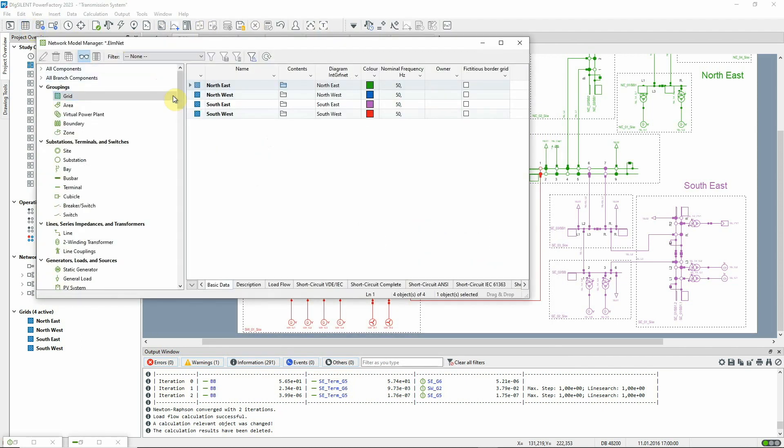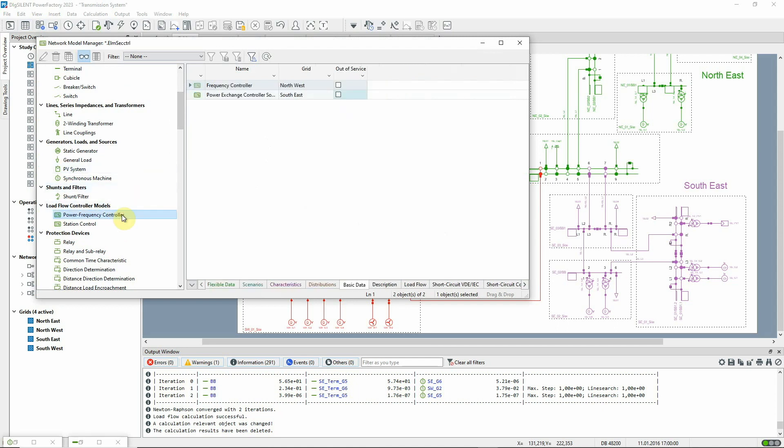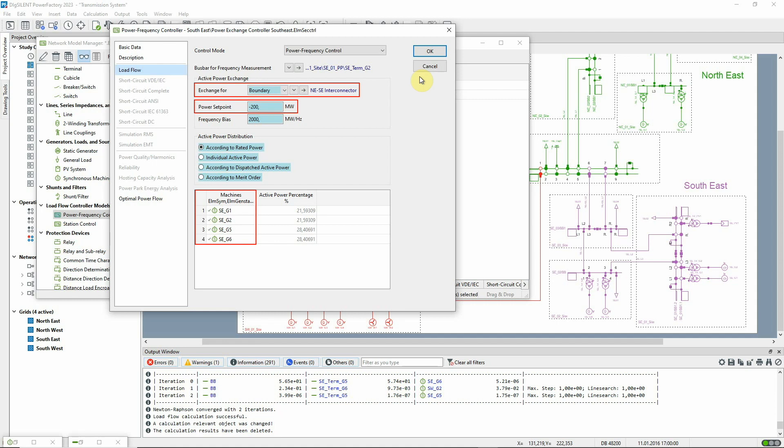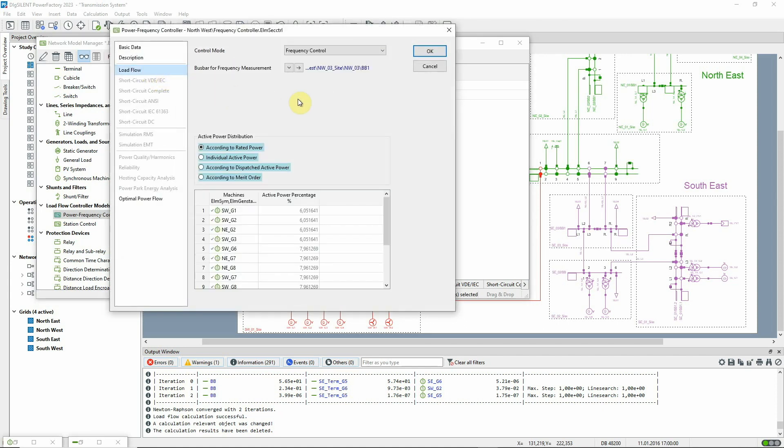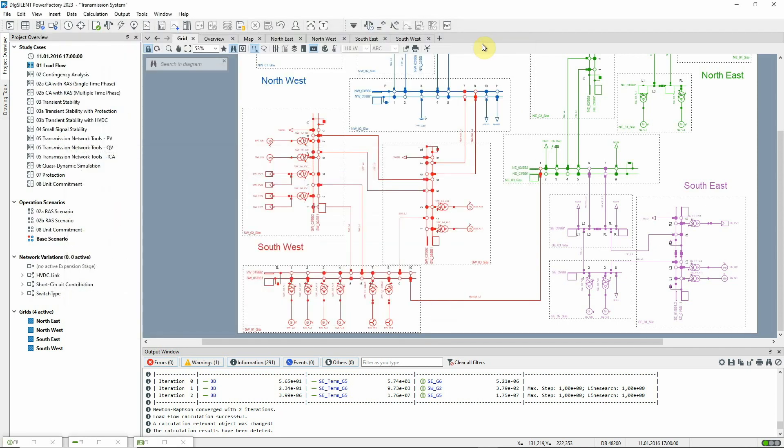In this model, there are two power frequency controllers, which can be seen in the network model manager. One controls the four synchronous machines in the southeast to maintain the flow across the northeast-southeast interconnector boundary to a specified value. Here, the value is set to minus 200 megawatts. The other controller controls the remaining synchronous machines so as to balance the network. In this case, dispatching them according to their rated power.